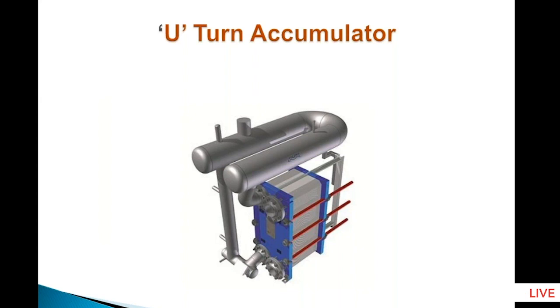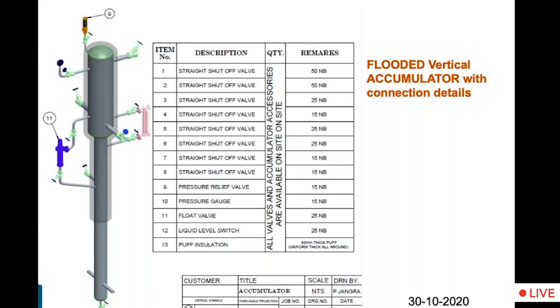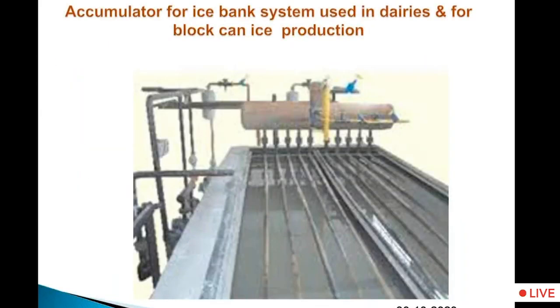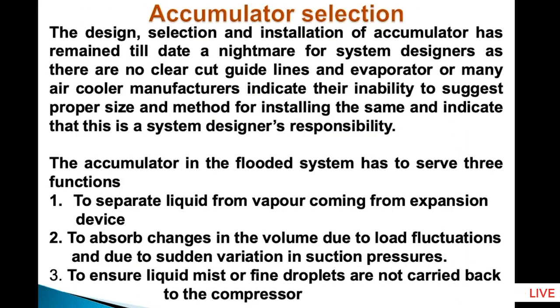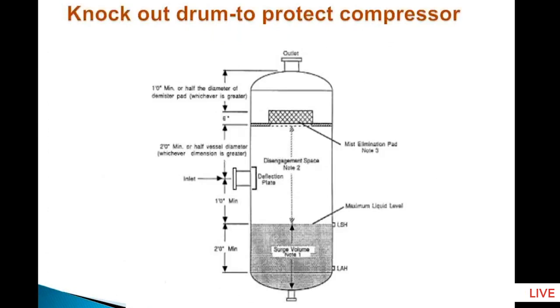So to avoid all these problems, Alfa Laval, their PHE, if you see, they give along with the accumulator a U-turn accumulator. And I've used this U-turn accumulator in many places, and it has given me satisfactory service. So this U-turn accumulator is available only with Alfa Laval. This is their patented design for the PHE, ammonia PHEs. This is an accumulator design. This is an ice bank system with the accumulator, and this is accumulator selection, as I mentioned, accumulator sizing.